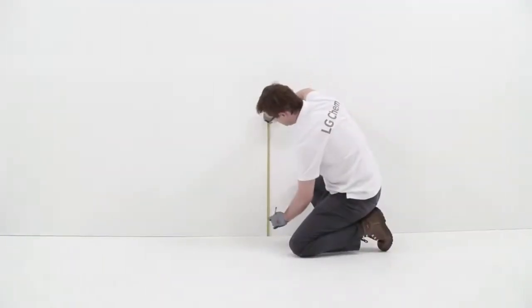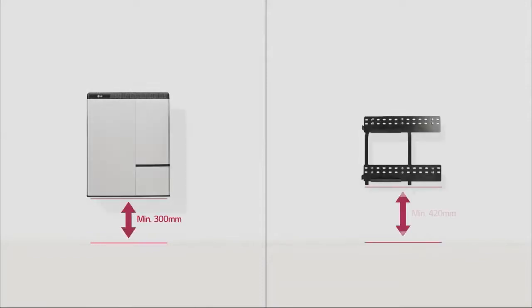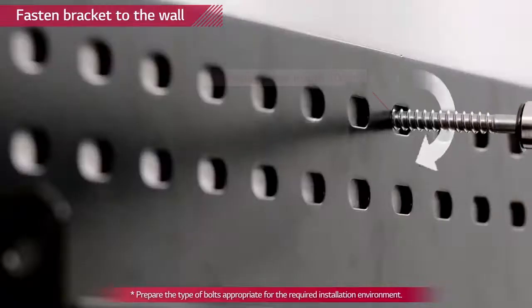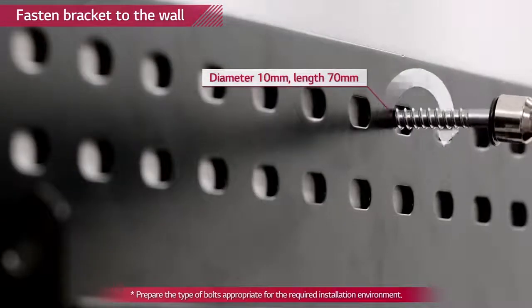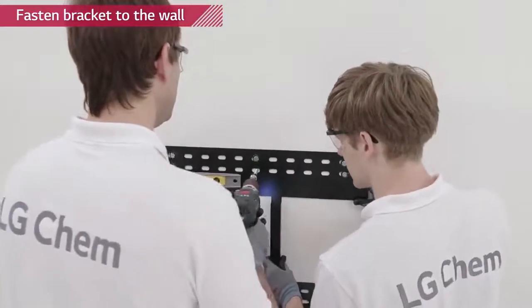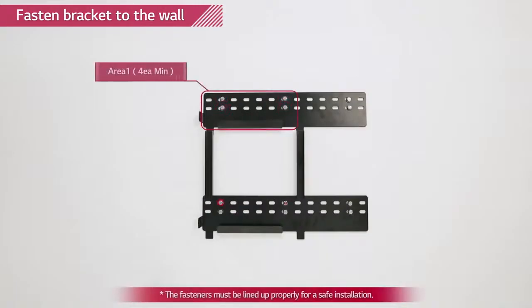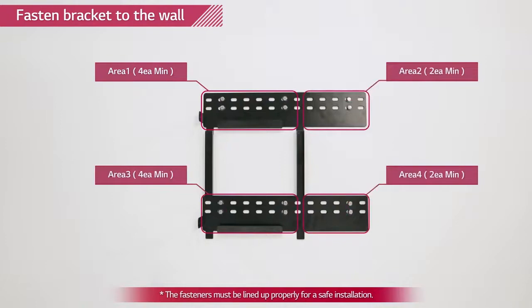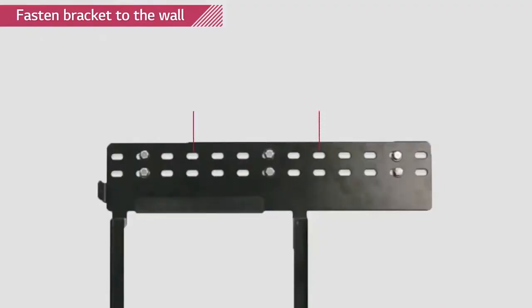First, the wall mounting bracket needs to be fixed. Please note that the RESU 7H and RESU 10H can only be wall mounted. Mark the location on the wall by placing the bracket to the wall and then drill anchor screws to the wall. Use at least four bolts for area 1 and 3, and at least two bolts for area 2 and 4. The distance between bolts in area 1, 3, and 4 must be at least 250 mm. The wall mount bracket must be leveled.